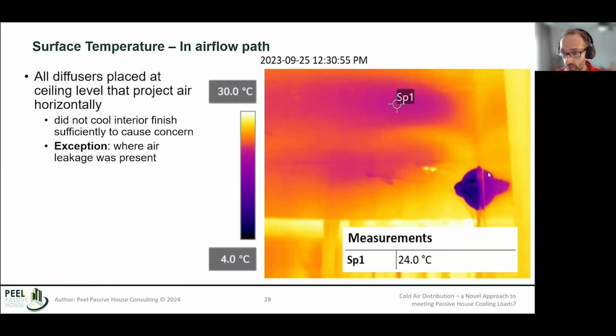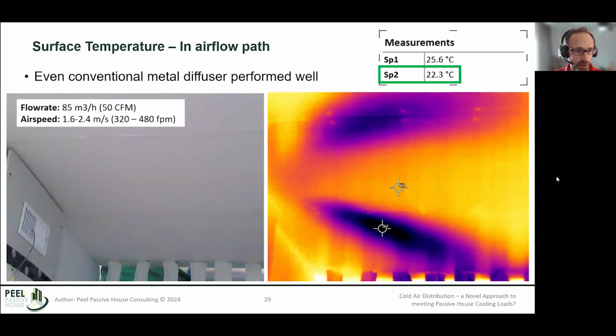So we have it both around the diffuser and also if we look in the airflow path, right? So along the ceiling, you can see here 24 degrees C. So what is that, 78 or something Fahrenheit? Really high. So this is 5-degree air coming out of the diffuser and right into the ceiling right above it, where there's barely any difference from the room temperature, which is pretty incredible. So as long as we don't have air leakage around the diffuser coming out in areas we don't want it coming out of, this is actually a good strategy.